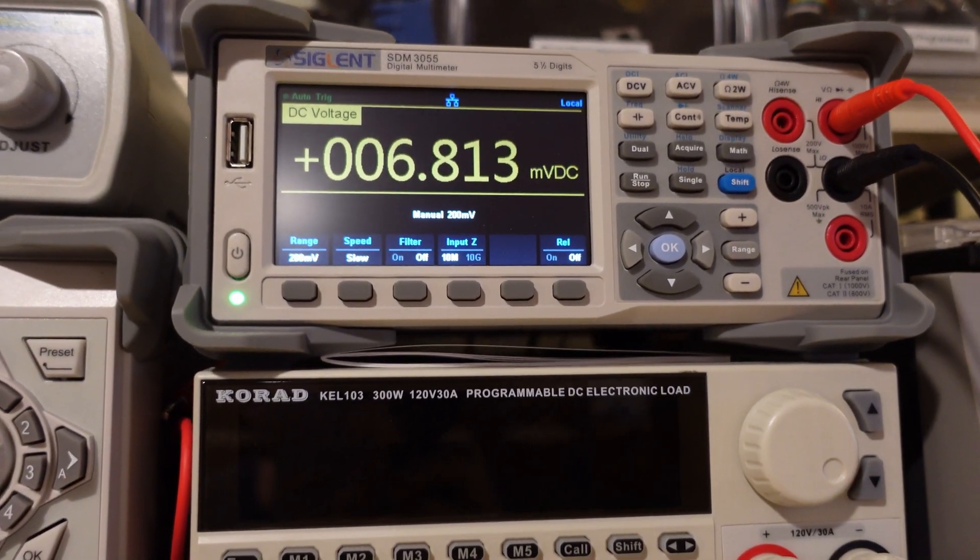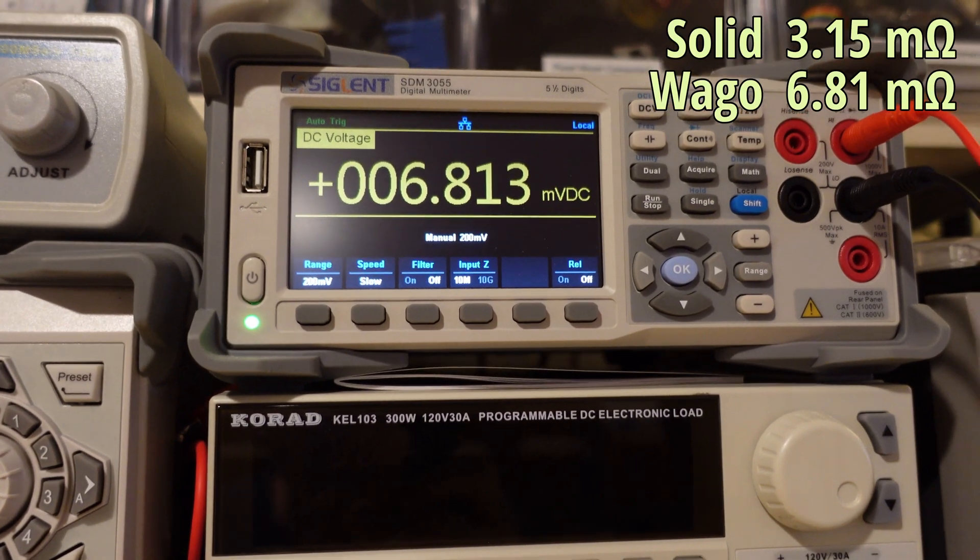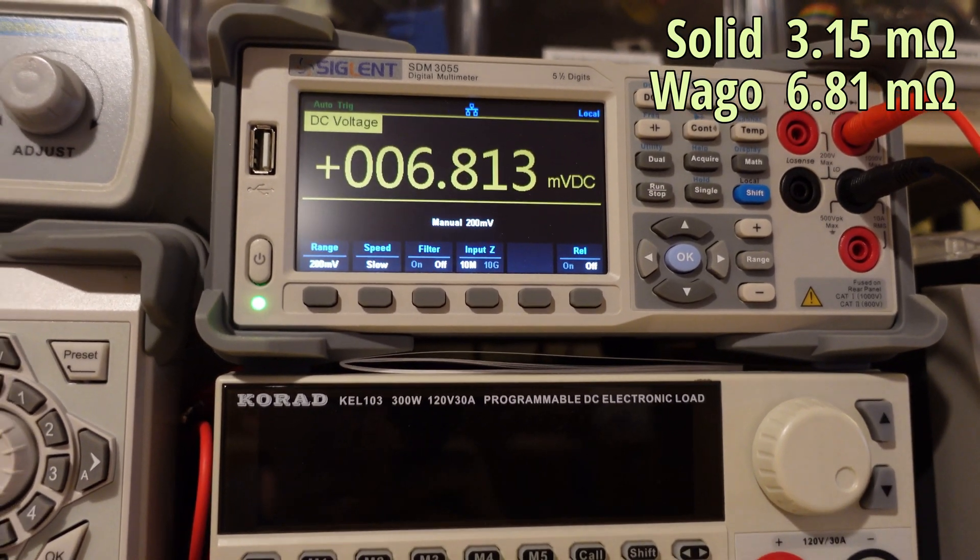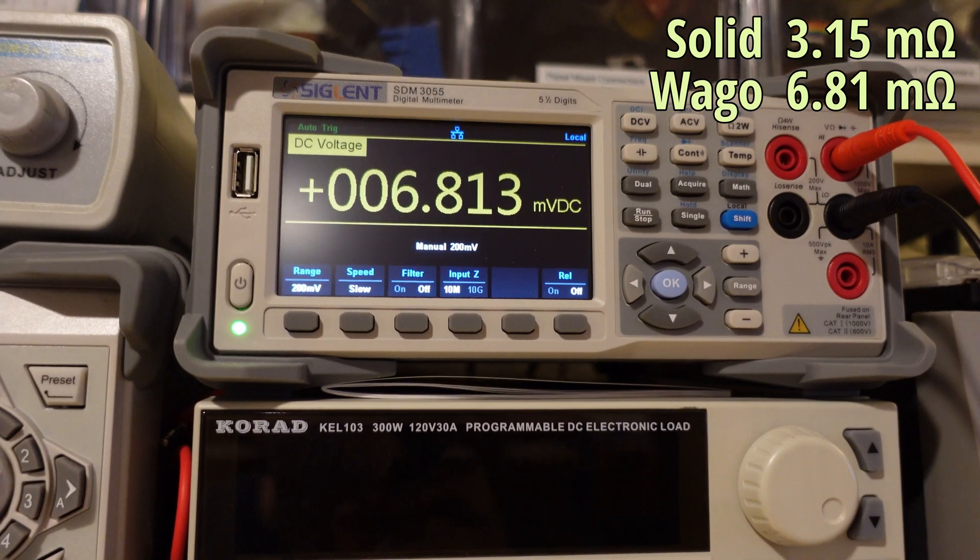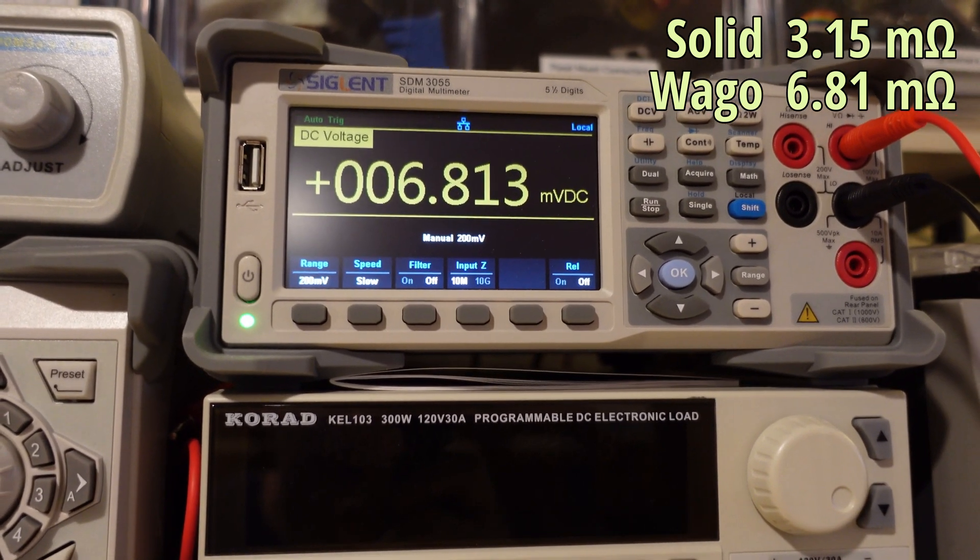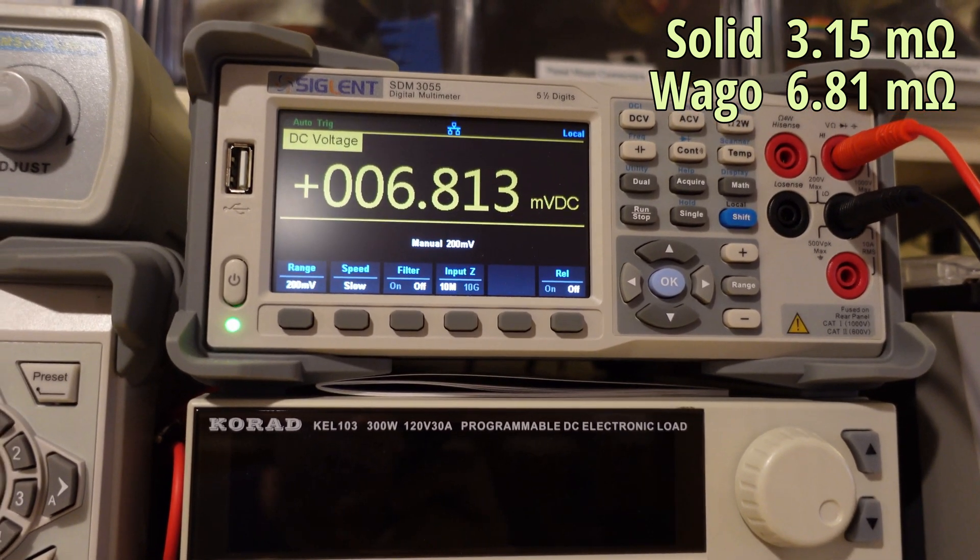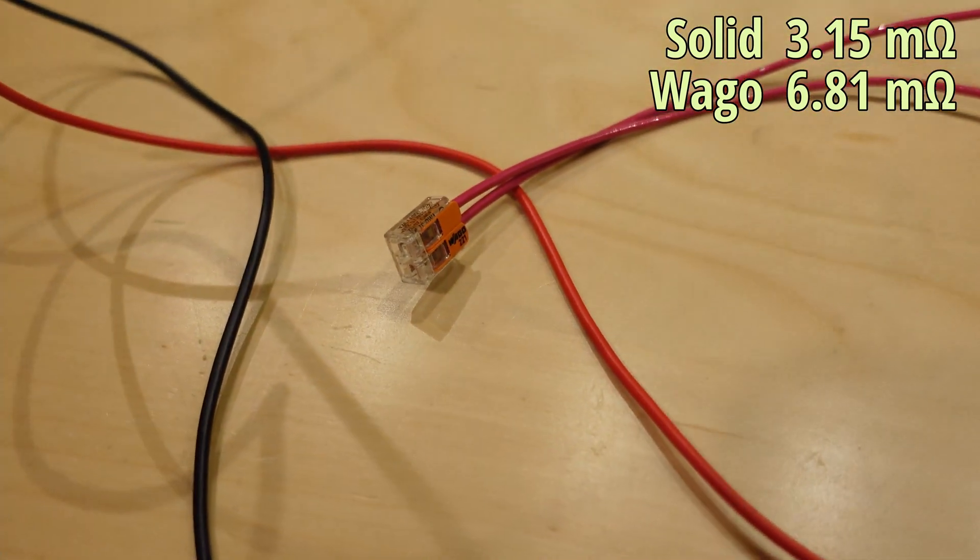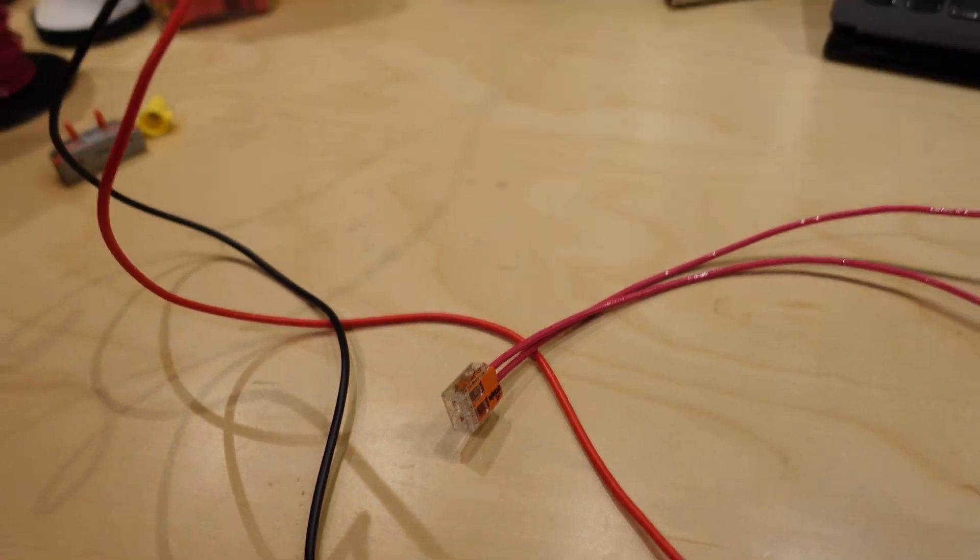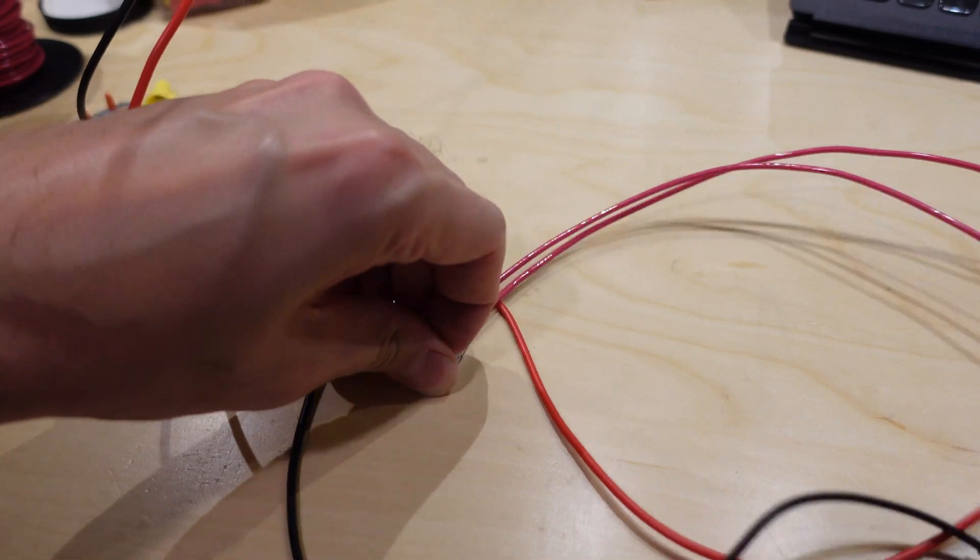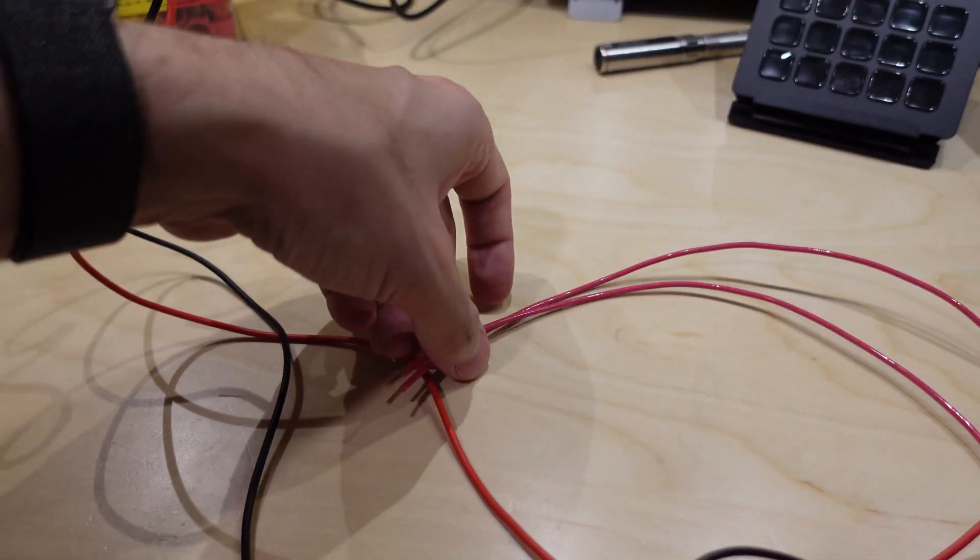So let's, realistically, let's call it 6.8. So if you went from 3.2, 3.1 to 6.3, then we really only have 0.5 milliohms of resistance added by this WAGO, which is pretty impressive considering what's inside of it. So let's take the WAGO off. We'll put, before we put a wire nut on, let's do a quick experiment.